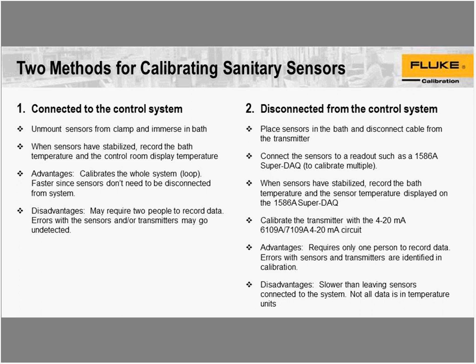So in the first method, the temperature sensor is connected to the control or measurement system. In this case, you take this out of the clamp, put it in the bath, and the display provides the actual temperature of the sensor. Then you go to either the control room or the PLC display, or whatever the control display is, and you see what the control room is measuring for the temperature sensor. Then you can make adjustments and take data again to verify that everything is good to go.